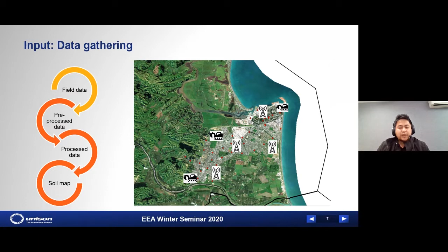What we've done is create a web form that a tester can key data into, generating a thermal dryout curve which we can then use for rating studies. We collect three different sets of properties - the three key ones being soil resistivity, moisture content, and the type of soil.